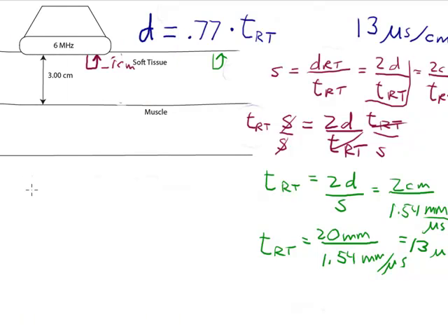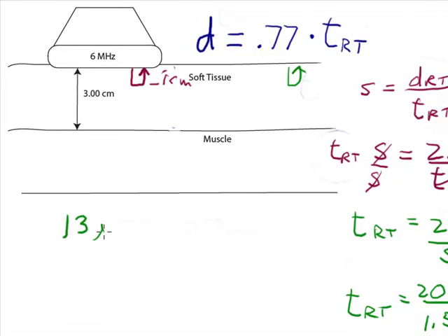The time it takes for an echo to go down 1 cm and return is equal to 13 microseconds. We can use the rule 13 microseconds per centimeter. If the reflector is 1 cm away, it's going to take 13 microseconds for the echo to return.